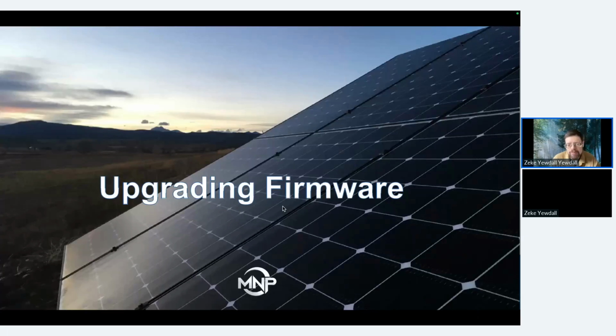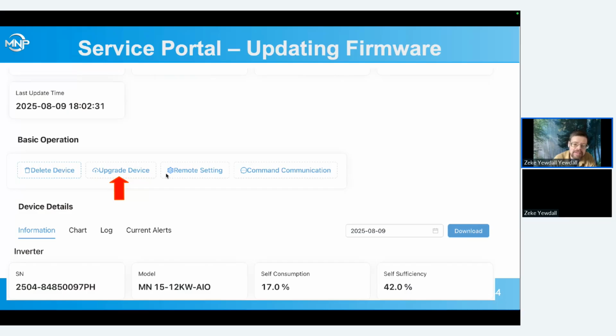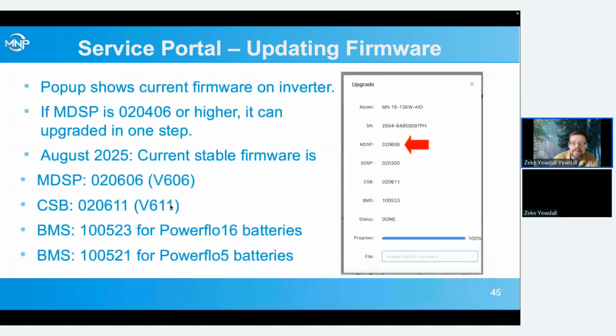Upgrading the firmware is also done from the portal. And that's this button here, upgrade device. If we click on that, it'll bring up this little box on the right here, and it'll show us what our current firmware is. The MDSP and the CSB, those are kind of our two main numbers we're looking at. And then BMS is the firmware of the batteries. If it's currently 406 or higher, we can upgrade it in one step to the current level. And if it's an earlier version, we'll have to do it in multiple steps.